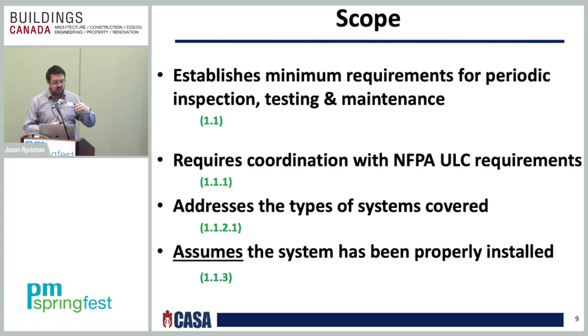Basically, with any standard, there's the scope and purpose, which is very important information that you have to understand whenever you're looking at an NFPA standard. The scope of NFPA 25 covers the administrative requirements for the periodic inspection, testing, and maintenance of water-based fire protection systems.